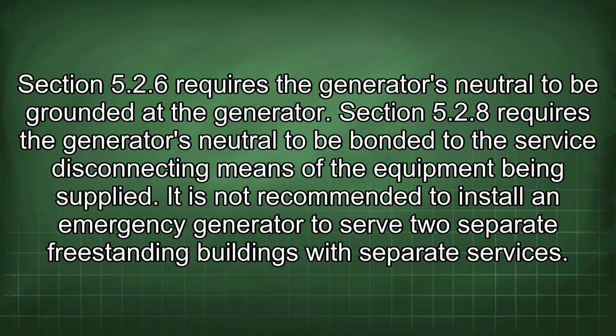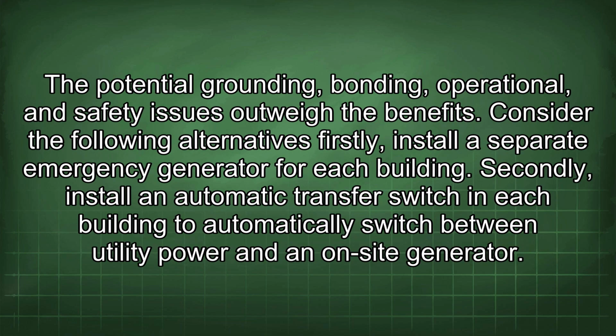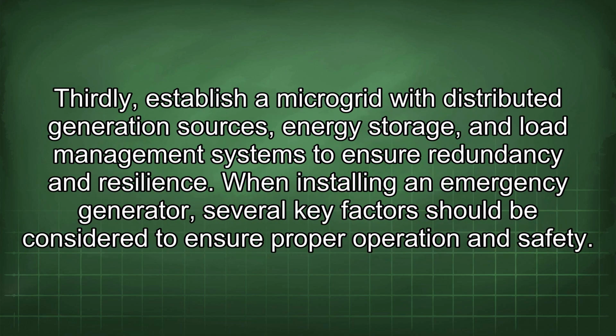It is not recommended to install an emergency generator to serve two separate freestanding buildings with separate services. The potential grounding, bonding, operational, and safety issues outweigh the benefits. Consider the following alternatives. Firstly, install a separate emergency generator for each building. Secondly, install an automatic transfer switch in each building to automatically switch between utility power and an on-site generator. Thirdly, establish a microgrid with distributed generation sources, energy storage, and load management systems to ensure redundancy and resilience.